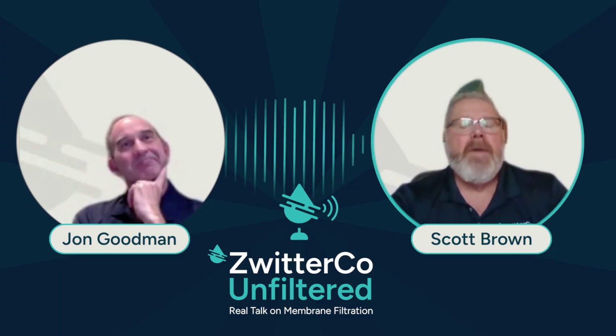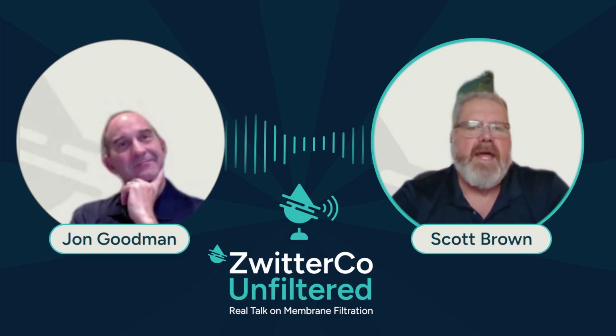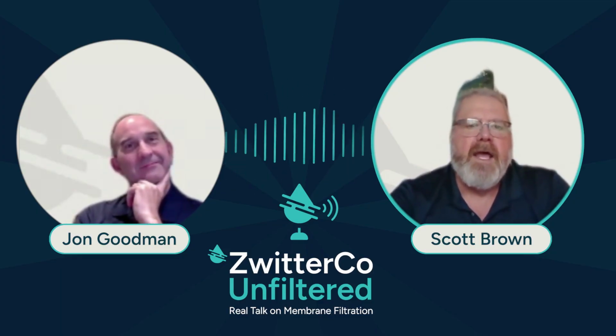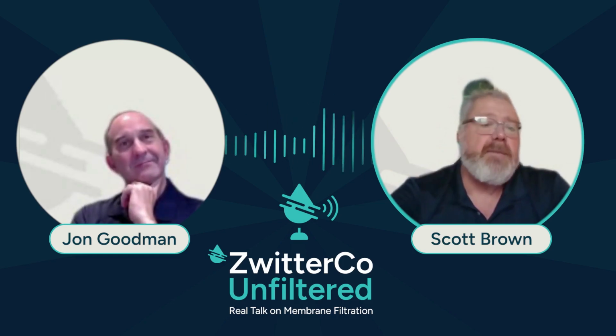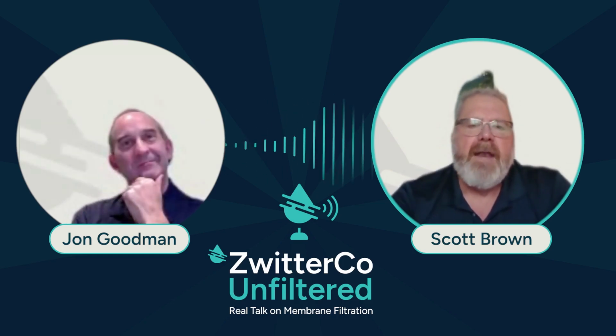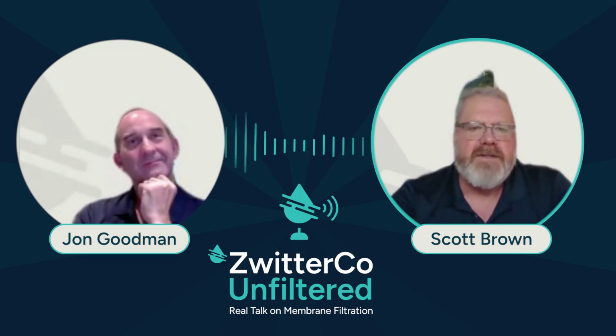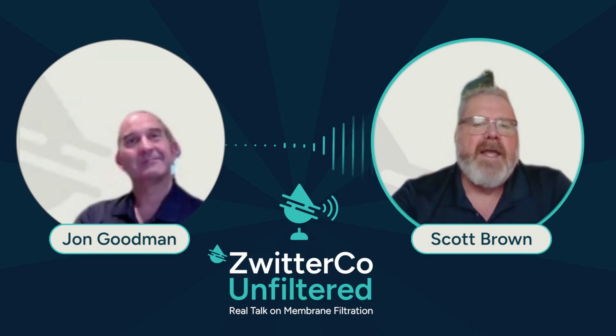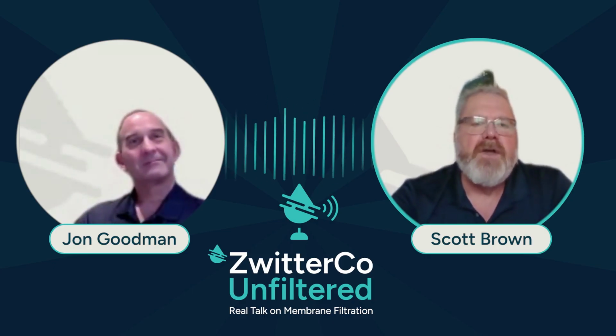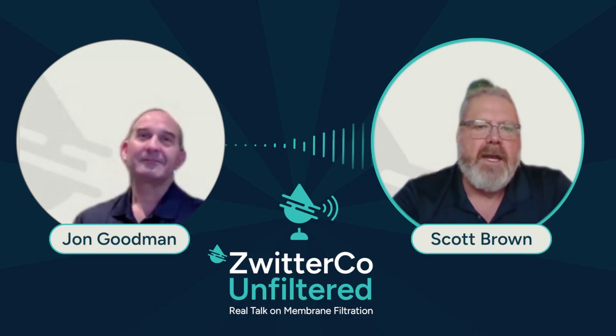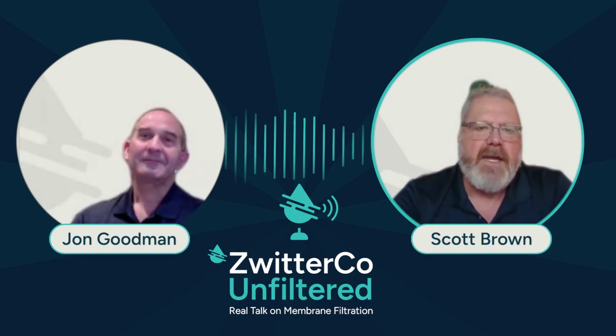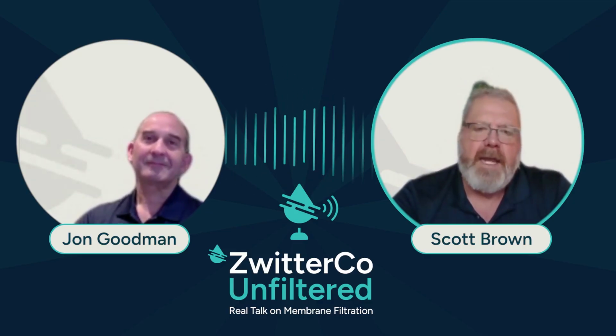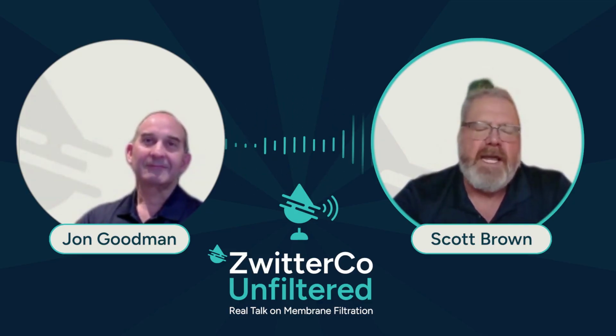They are. As a matter of fact, I was in a plant earlier this week where they had a mixture of RO and NF elements in the same system, in the same stage. And they're still doing that. And they're doing it effectively. And they're driving the solids harder and higher. Again, the permeate becomes an issue because now you've got more mineral, more ash in it if you have the NF elements, right? But again, we just take that permeate and put it into a different system. We reclaim all of the solids.